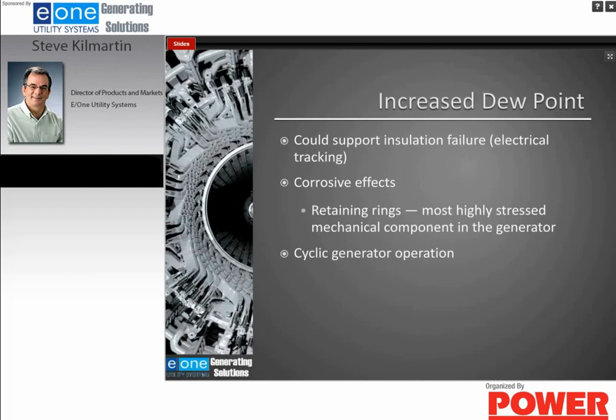One other thing is, years back, when I got back into this business, most generators were base load units. They came up, they ran, and you didn't take them offline until your outage. Nowadays, there's a lot of cycling that takes place with generators. There are a lot of combined cycle plants and peaking units that will operate once or twice a day, for a couple of hours. The problem with this is that the gas in the generator is heating up and cooling down, and that heating and cooling effect can cause the moisture in the generator to condense. So the high dew point, along with cycling of the generator, could cause problems in the generator.